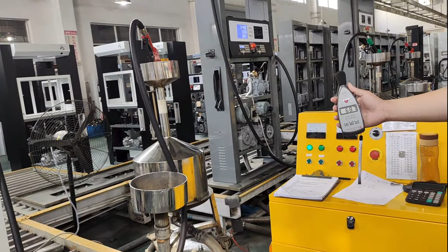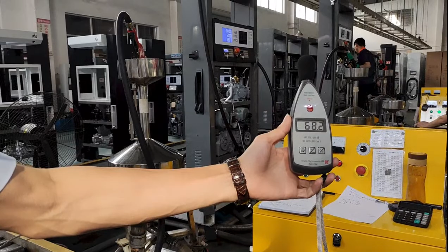The level you can see is for testing noise. Later we will check. The noise standard is less than 80. We can see this is the noise we just tested from the machine. Less than 80. Yes, so we can pass.